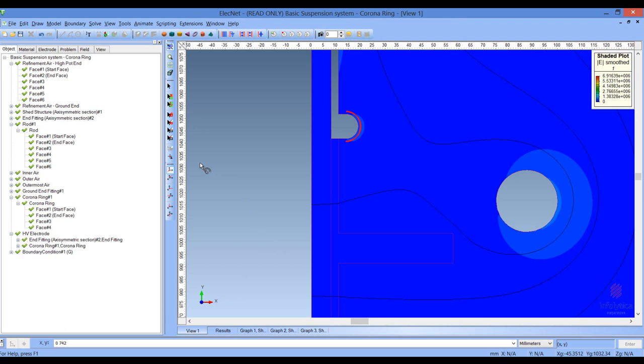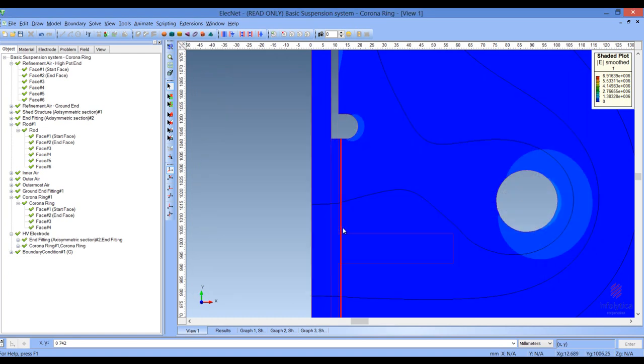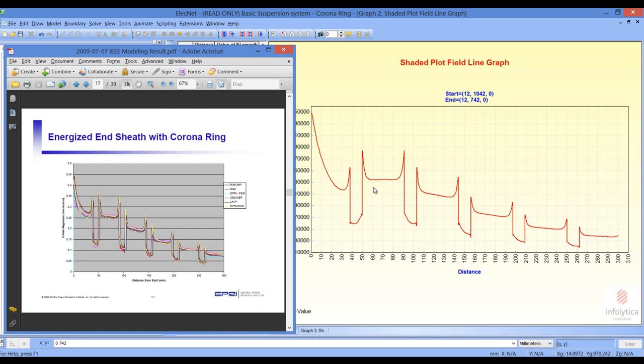Let's look now at the second contour — the contour taken at one millimeter from the outside sheath. The results are shown in this chart. The first thing we note is that the corona ring has a tendency to reduce the electric stress around the end fitting and the shed as well. You can see how it has dropped considerably, and comparing to the results from the EPRI report, they compare quite reasonably.